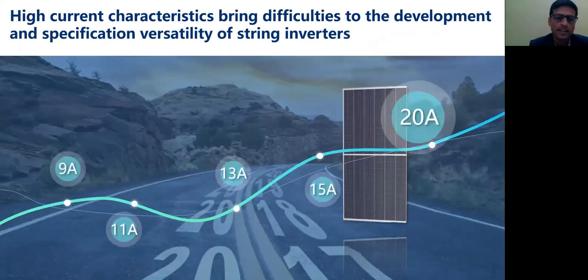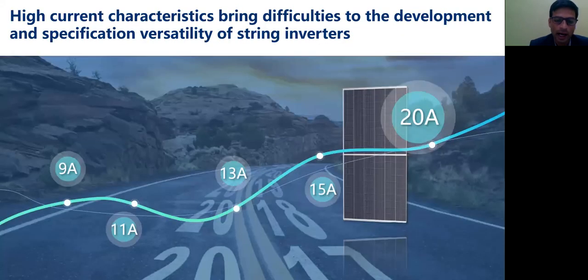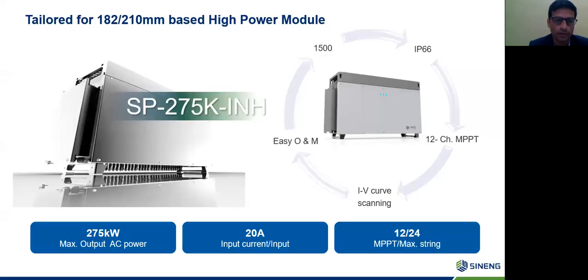So to understand the power increment with the increment of wafer size, a PV cell is an irradiance controlled current source. Current can be increased either by increasing the irradiation or cell area. So we can say the larger the cell area, the larger the current. For utility projects, now system voltage is 1500 volt. Though the cell area increases, voltage remains the same due to half cut technology.